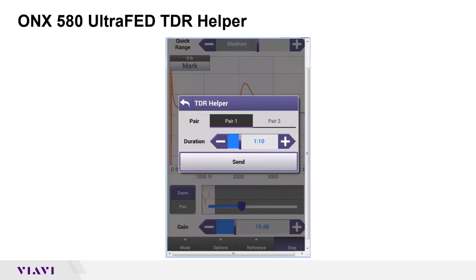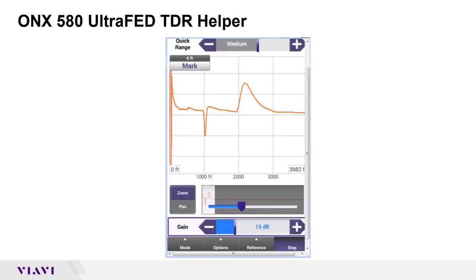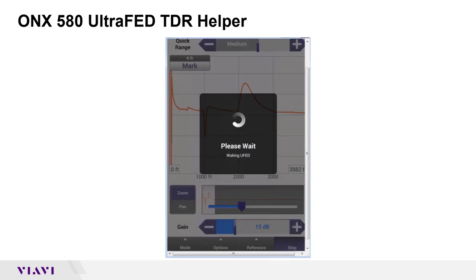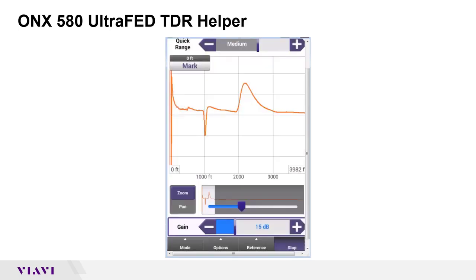You'll notice you've got a duration setting for how long you want it to short the pair and then open the pair. I don't want it to stay on for a minute and 10 seconds, so I'm backing it down to about 25 seconds for the demo. I've got pair one connected — I could connect a second pair for comparisons if needed. I'm simply going to hit Send. Once I've done that, it sends DTMF tones out and wakes the far end device up.